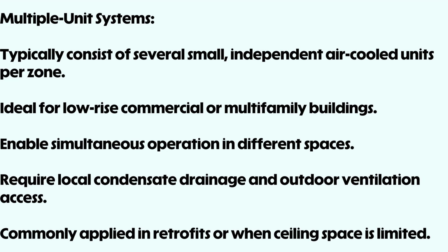Multiple unit systems combine several self-contained units distributed through the building, each serving a specific zone or floor. They can be air or water-cooled and are commonly used in offices, apartments, and schools. Advantages include flexibility, modularity, and ease of servicing. Units can be relocated or replaced individually, reducing downtime. However, they require outdoor air access for ventilation and may occupy more mechanical space than centralized alternatives.